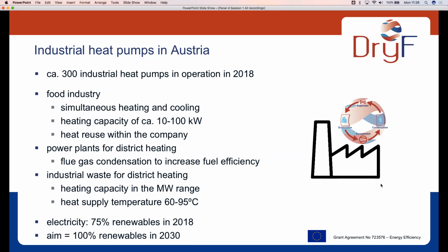Another important field of application are power plants that provide heat for district heating. In those installations, we find heat pumps for flue gas condensation. They use the heat pumps to recover the latent heat that is still available in the flue gas to increase the fuel efficiency of the power plant. And the third group, which is also gaining importance, are heat pumps that make use of industrial waste heat and also supply district heating. This is mainly due to the fact that district heating has a lower temperature range than the industrial process itself. Those installations usually have heating capacities in the megawatt range, and they supply heat with temperatures in the range of 60 to 95 degrees C.